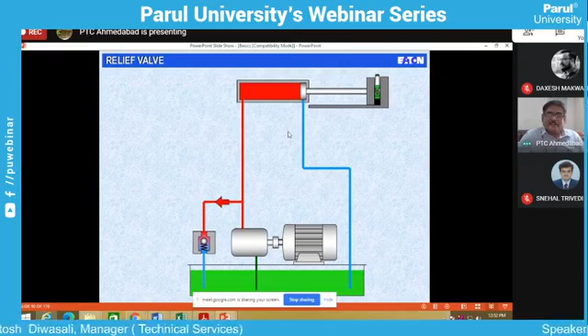Now another function is changing the direction of an actuator. As you can see over here, I have placed a valve which is known as a direction control valve. In this condition, the fluid is passing through it and going to the cylinder port, say port A, and the return fluid is coming back from port B to the tank, as you can see here as a blue color line. Suppose I shift this valve from one position to another because I want to change the direction of the actuator. This red color fluid now starts flowing through the direction control valve to the cylinder without changing any physical connection in the system, and this red color fluid is now at port B, and slowly it will start moving the piston, and this piston will be moved towards the left, as you can see over here.